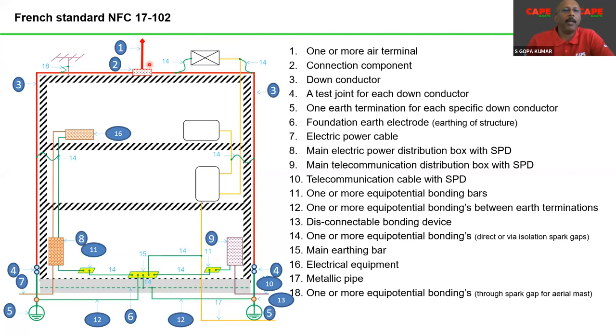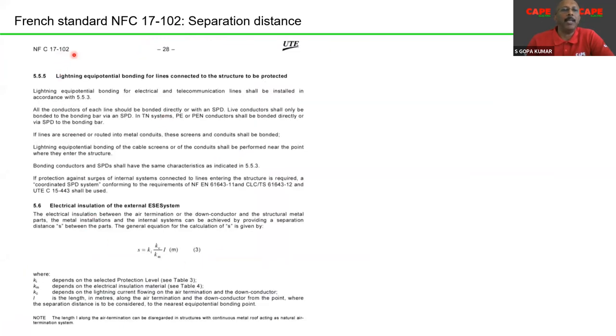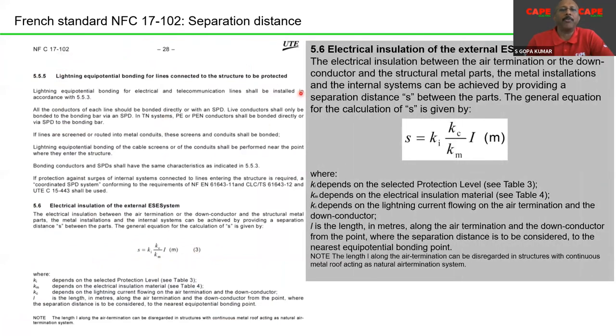This is never written in the National French Code. Now, anyway, our subject is not only that. Our subject is separation distance. In the same French Code, you can find the separation distance calculation. Say, for example, clause 5.6, separation distance S equals Ki divided by Km into Kc into L. The same calculation which is included in the IS IEC 62305.